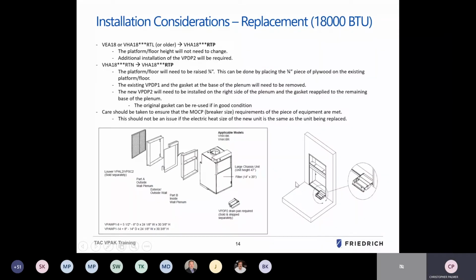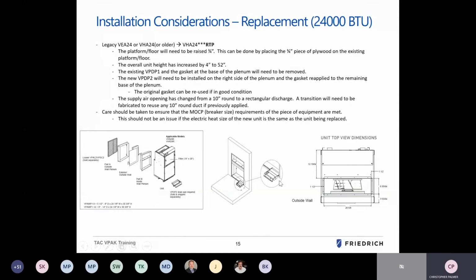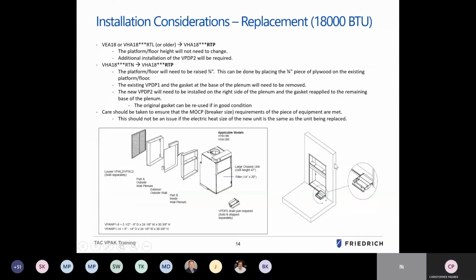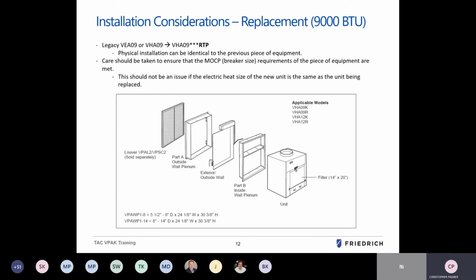Now, be mindful that we do have two different wall plenum sizes that can go up to 14 inches in wall depth. So when ordering those plenum kits, make sure you size them appropriately for, oh, I slipped ahead here. Sorry, my apologies, still stuck on 09. That's the VPA WP1 8 and then the VPA WP1 to 14. So that those two plenum pieces do slide back and forth between each other and can be sealed appropriately with the appropriate silicone and screws, fasteners, to make sure that they seal tight against the wall exterior and the inside wall drywall.